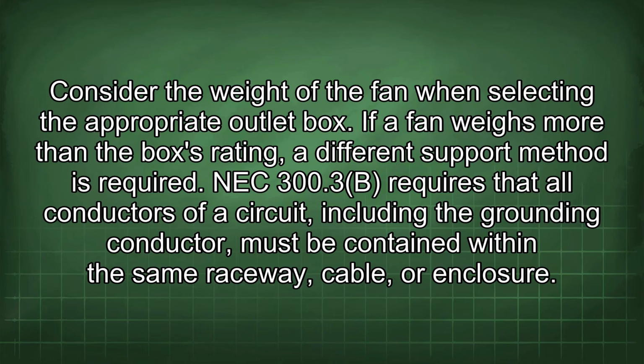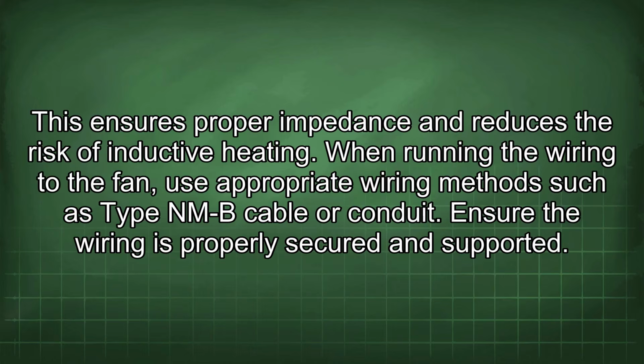NEC 300.3(B) requires that all conductors of a circuit, including the grounding conductor, must be contained within the same raceway, cable, or enclosure. This ensures proper impedance and reduces the risk of inductive heating. When running the wiring to the fan, use appropriate wiring methods such as type NM-B cable or conduit. Ensure the wiring is properly secured and supported.